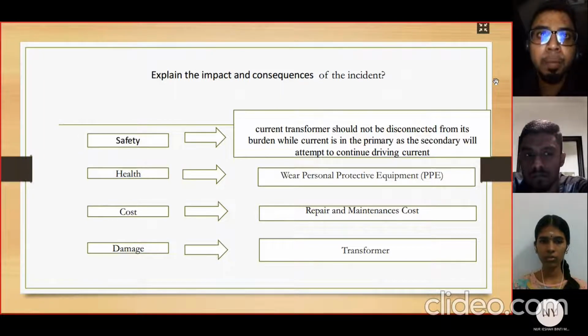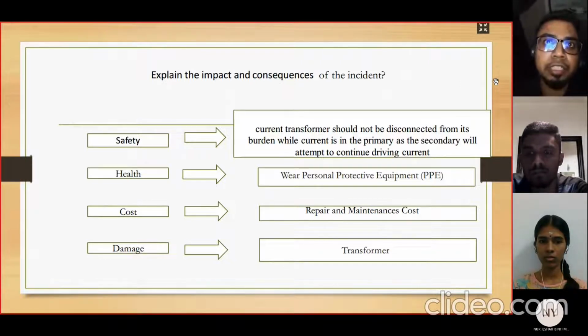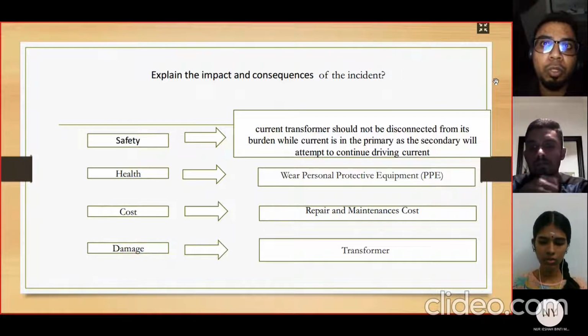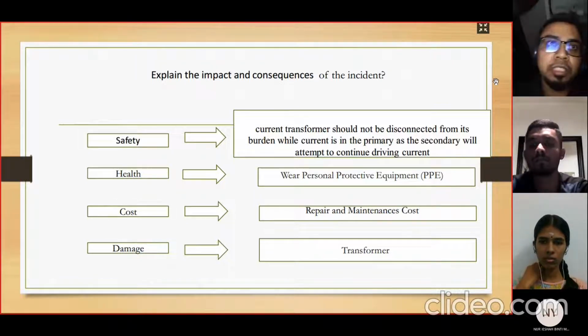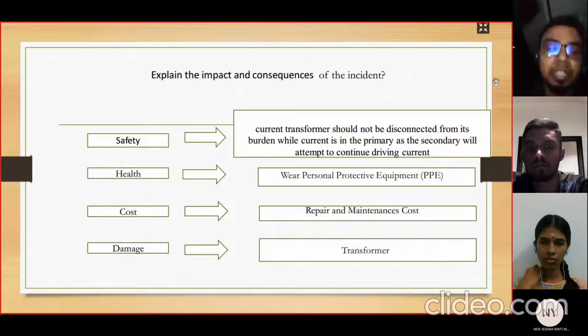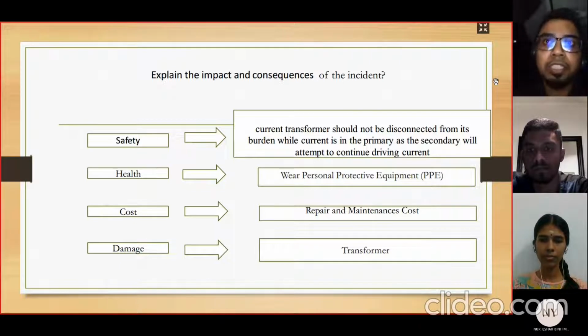Third is cost. Based on the incident that happened, the cost will be for the repair and maintenance, as the transformer has totally gone down due to the incident. It will be one of the biggest consequences if an event like this happens elsewhere. Last is transformer damage. Transformer number 6 was damaged due to this incident at Bayswater, while the other equipment is still intact and ready to use.